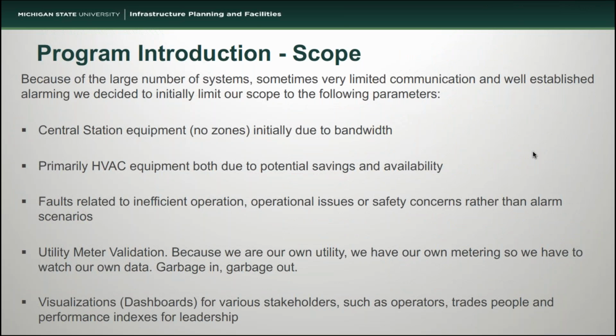So because of these factors where we're generating a lot of our own utilities, we have a very engaged central control operational staff and sometimes very limited communications. We aimed our scope pretty specifically at just the large pieces of equipment, so air handlers and chillers and heat exchangers, but not really at the sort of things that tend to condition rooms, because we weren't sure that we could bring that kind of bandwidth in and what kind of effect it would have on our system health. We also wanted to focus primarily on HVAC equipment because HVAC equipment can be anywhere from 20 to 60% of the energy used in the building. And because we've already got these control systems in place, we have a lot of data that's already available for these systems.